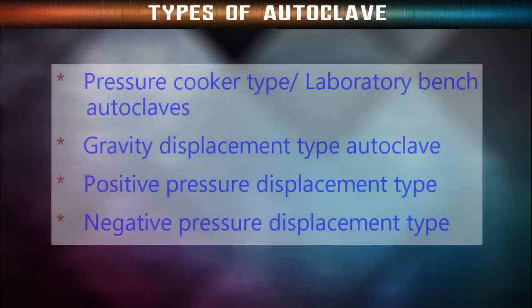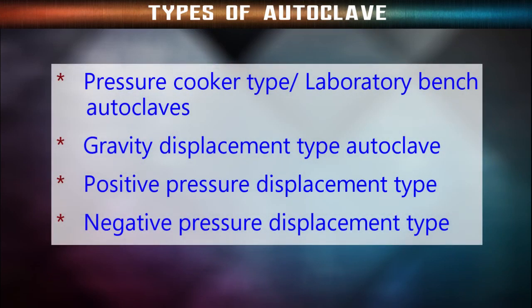Types of autoclaves are: first is the pressure cooker type or laboratory bench autoclave. These, like domestic pressure cookers, are still in use in many parts of the world. The more modern type has a metal chamber with a secure metal lid that can be fastened and sealed with a rubber gasket. It has an air and steam discharge tap, pressure gauge and safety valve. There is an electric immersion heater in the bottom of the chamber.